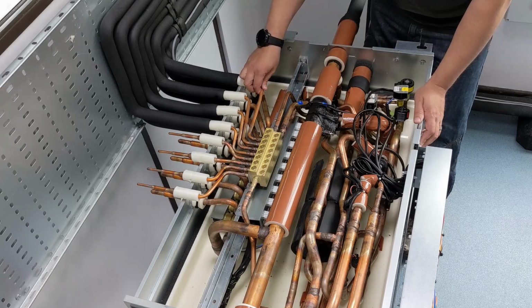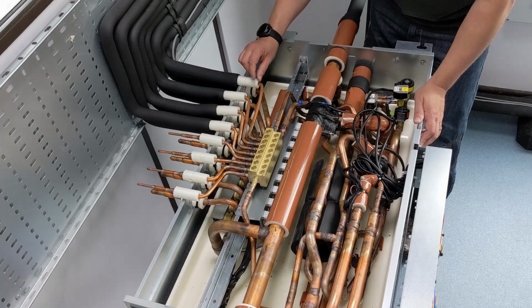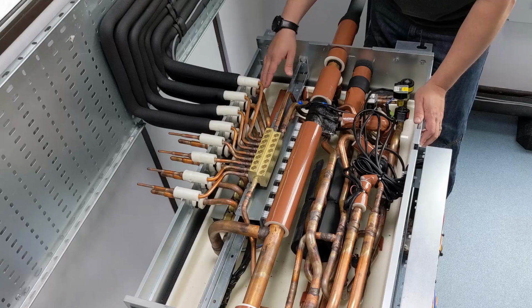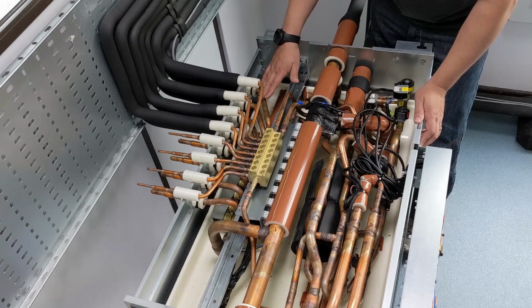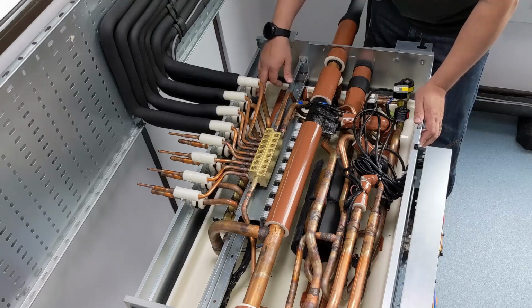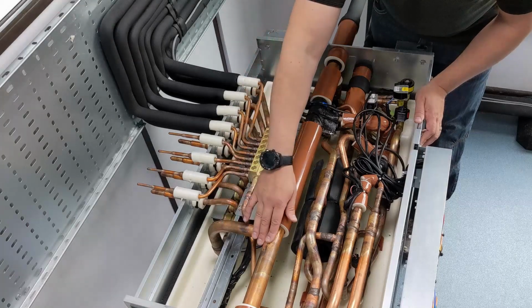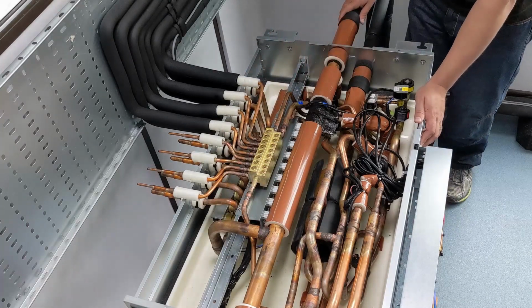As the indoor units get to within 2 degrees of set point, it starts backing down the expansion device, which means the low side of the system starts getting lower, so it's going to go below that 7.2 bar, so down to sort of 6 bars, something like that, at which point we actually slow down the speed of the compressor to bring that back to 7.2 bars. So that's how we're controlling the speed of that compressor. On the basis the indoor unit's working fine, we've boiled that refrigerant all off from being a liquid to all being a vapor, and so I've got the return leg coming back into the BC box, and that passes back off to the outdoor unit.